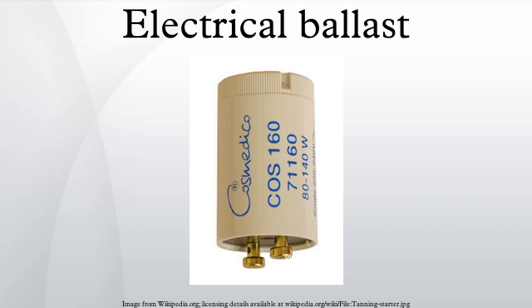An inductor is very common in line frequency ballasts to provide the proper starting and operating electrical conditions to power a fluorescent lamp, neon lamp, or high-intensity discharge lamp. The inductor has two benefits: its reactance limits the power available to the lamp with only minimal power losses, and the voltage spike produced when current through the inductor is rapidly interrupted is used in some circuits to first strike the arc in the lamp. A disadvantage is that current is shifted out of phase with the voltage, producing a poor power factor. In more expensive ballasts, a capacitor is often paired with the inductor to correct the power factor. In ballasts that control two or more lamps, line frequency ballasts commonly use different phase relationships between the multiple lamps, which mitigates flicker and helps maintain a high power factor.